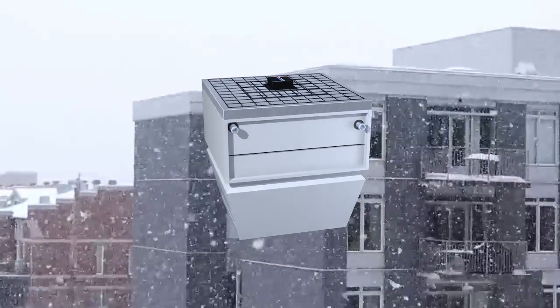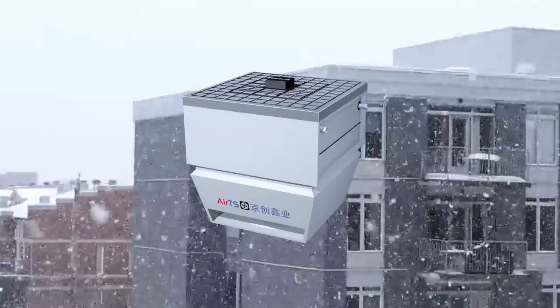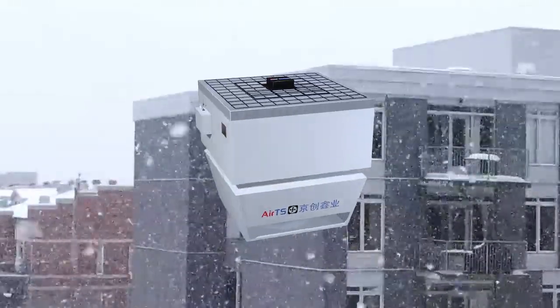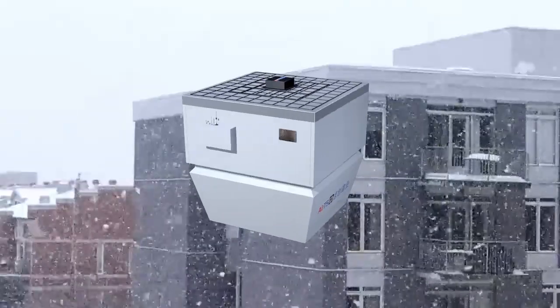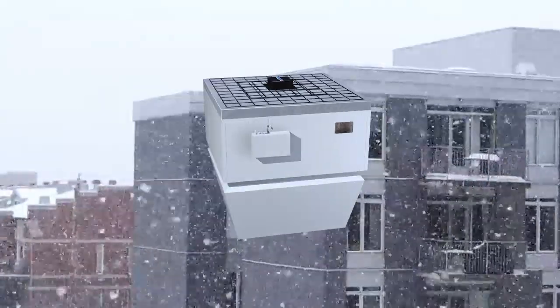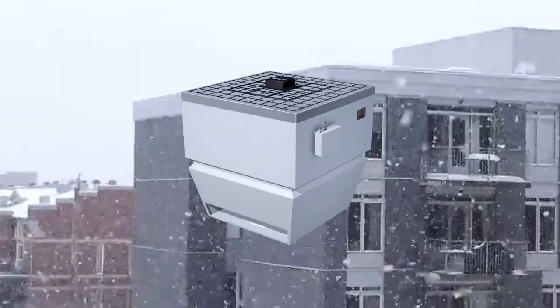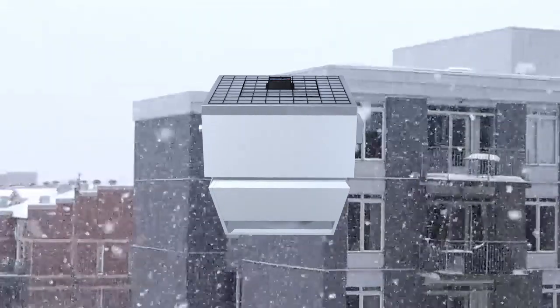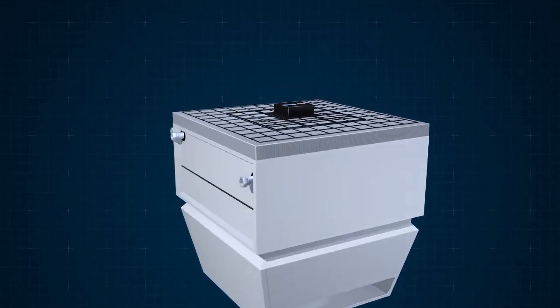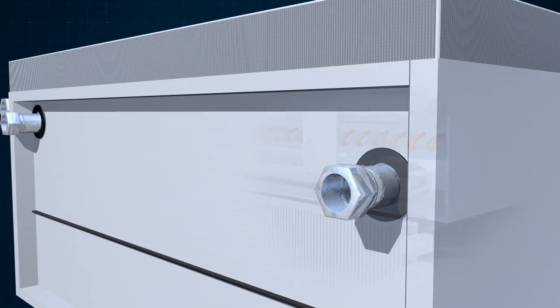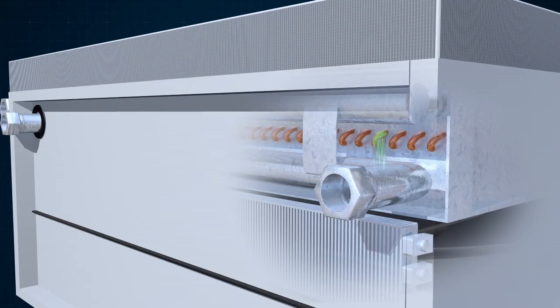When heating in winter, the air conditioning equipment, in case of severe cold air invasion or too low water supply temperature and short-term operation fault of water system, etc., is very likely to cause the risk of frost crack of heat exchanger, which may cause water leakage and affect the use of equipment.